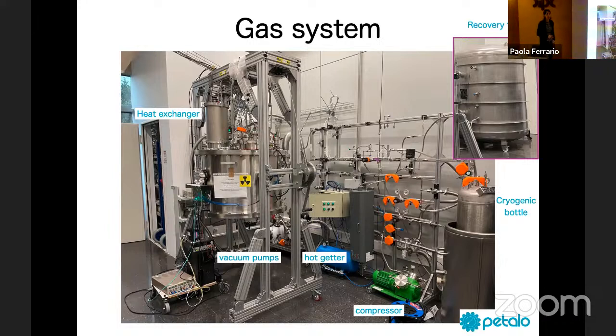This is basically for safety reasons, because if you have an overpressure in your system, we could just let the xenon go in the air. It is not toxic, it's no problem. The problem is that it is expensive, so we don't want to lose it. And it goes automatically to the tank. So this tank can host all the xenon that we have and more, at up to 3 bars of pressure.